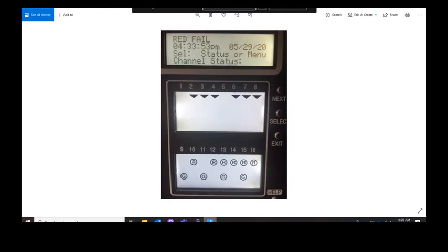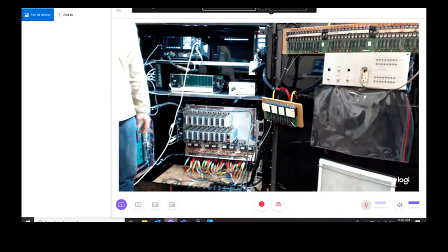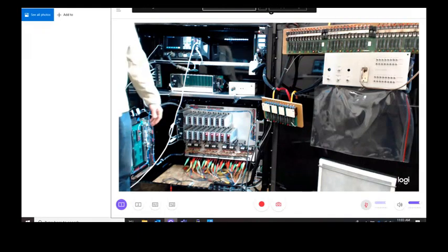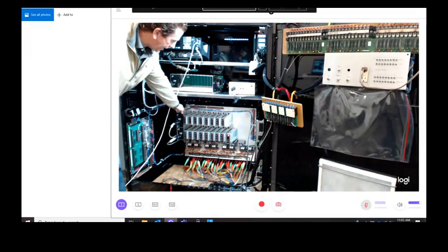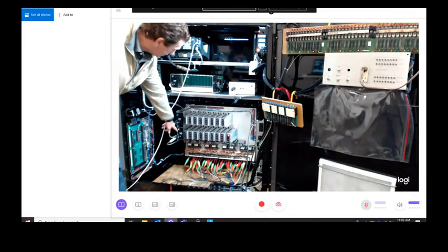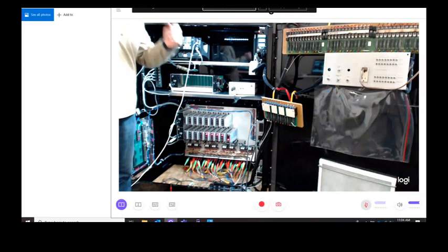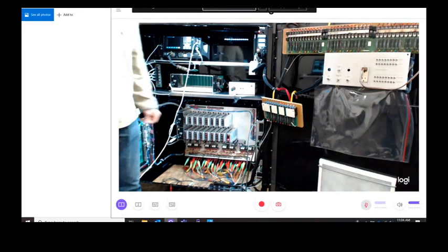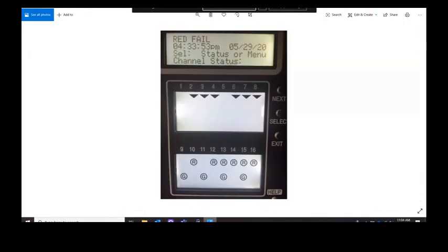This is a 16 position back panel, as you see, a little bigger than what you're used to seeing. We've traditionally always had 12 position back panels. If it was a 12 position back panel, the upper BIU number 1 would still do 1 through 8. BIU number 2 would only do 9, 10, 11, and 12 because that's the only ones that I have. So again, I lose 1 through 8 because of that.